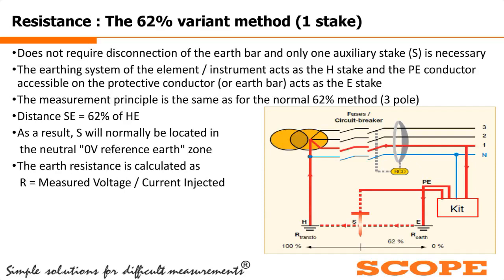Now, why is the distance between this auxiliary rod and this E stake 62% of the distance between H and E? Because by performing different trials and various experiments, this 62% method was formed, and it is also available in the different standards, because this 62% distance is referred to as the neutral or zero reference earth zone. So there might not be any influence in the measurement due to this type of rod placement. So this is the 62% variant method using a single stake.